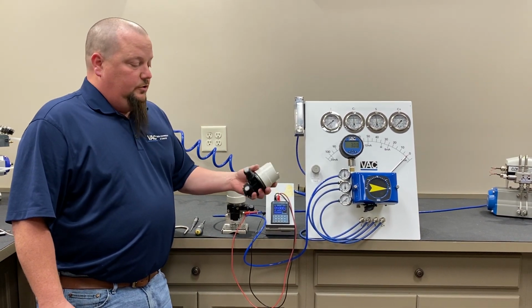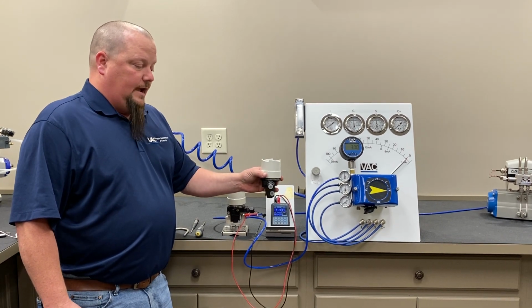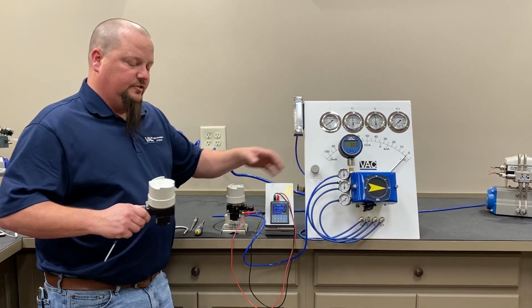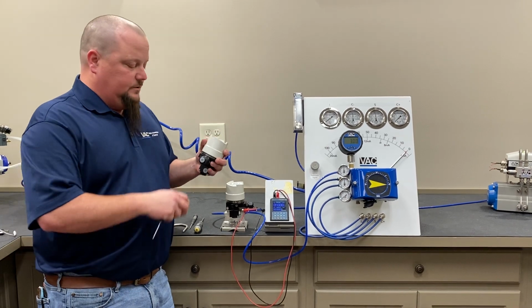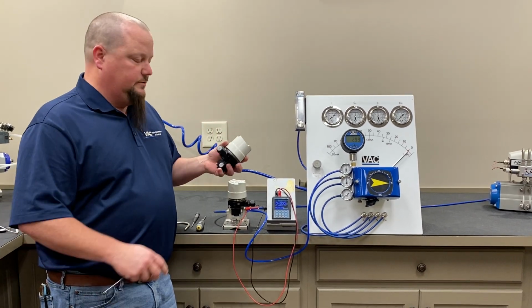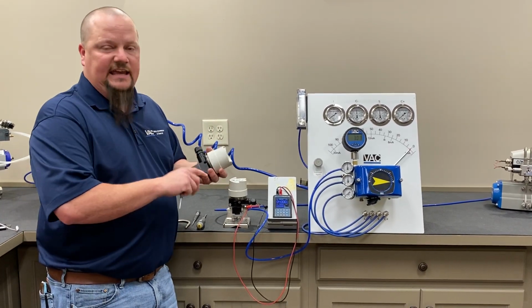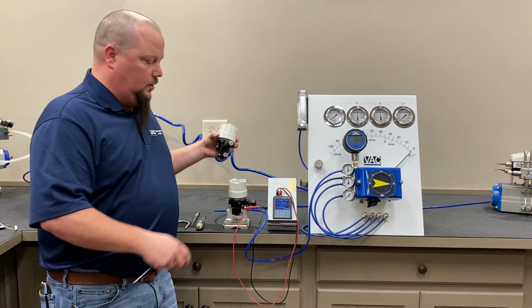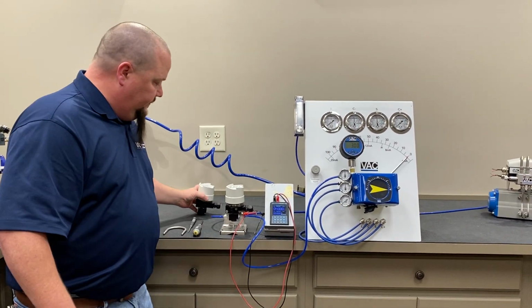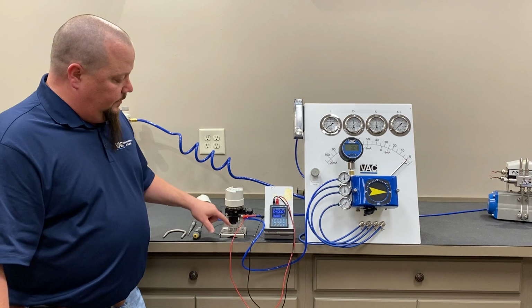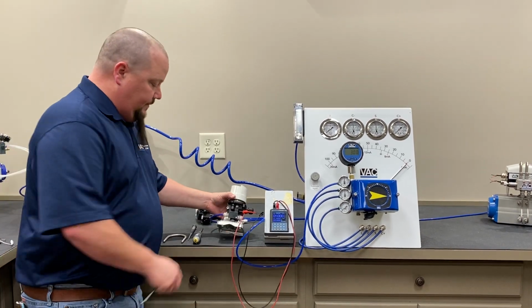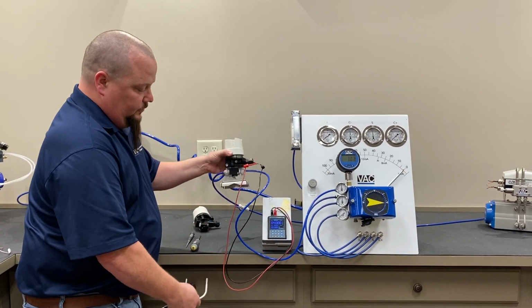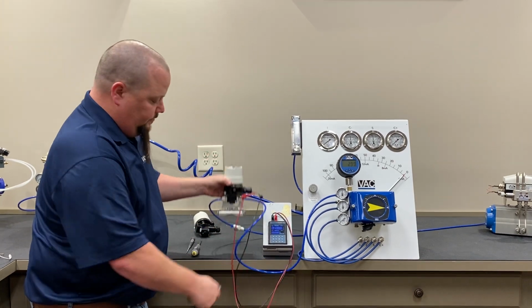What this allows you to do is mount your I/P separate from the positioner in an area or location for whatever reason, whether it's debris falling on the unit, heat, water, whatever. You can put it in an enclosure, or as we've got on the display model here, it's set up on a 2-inch pipe mount. It's already bolted to the pipe mount. You'll find the pipe you want to mount to, and you can mount the unit up.